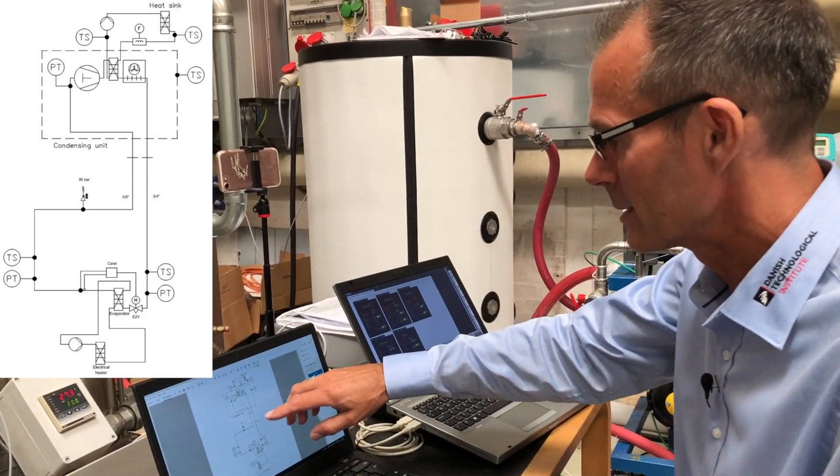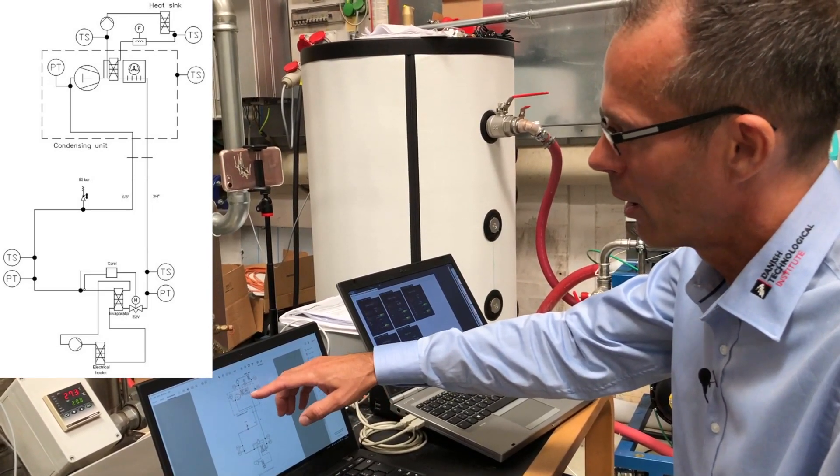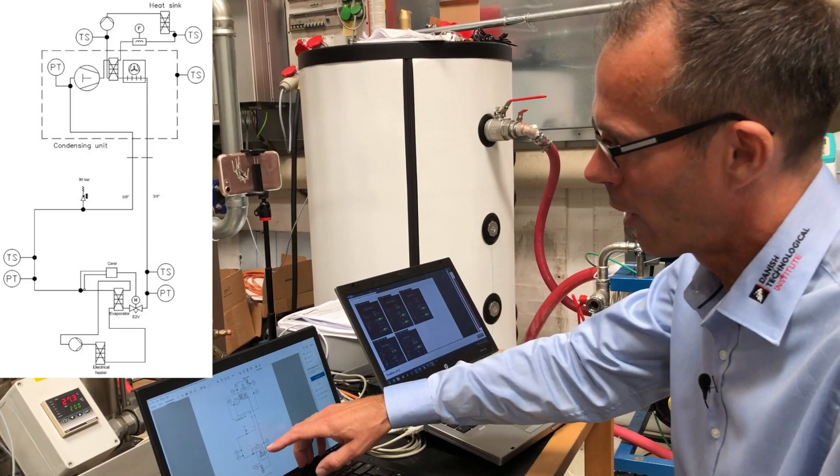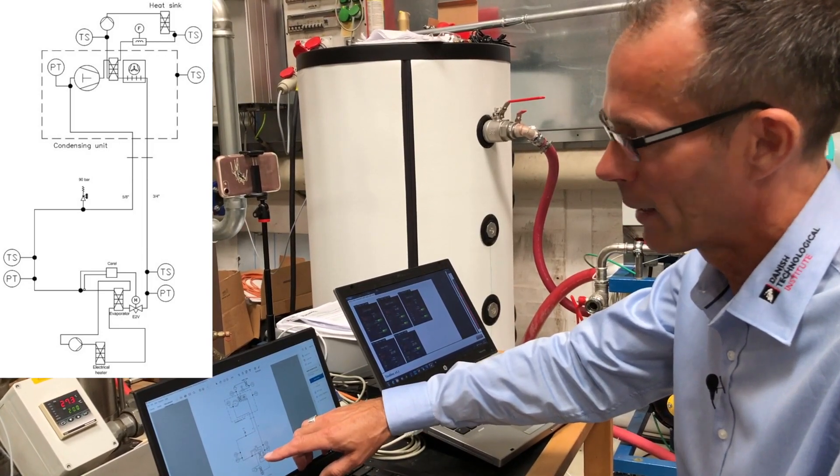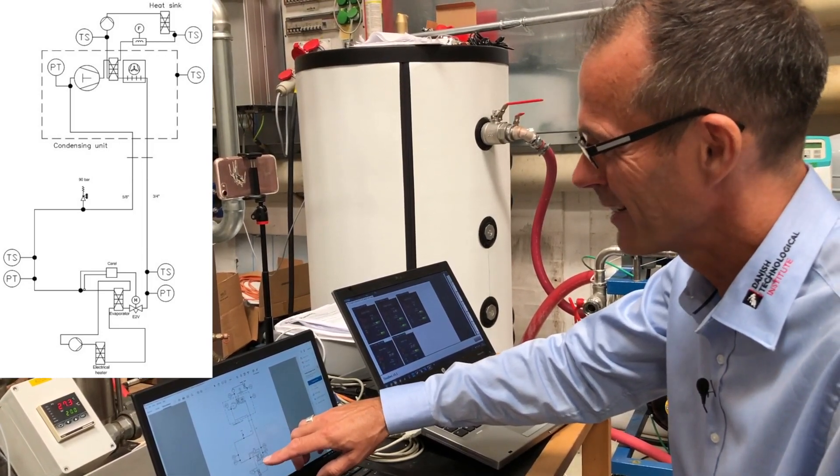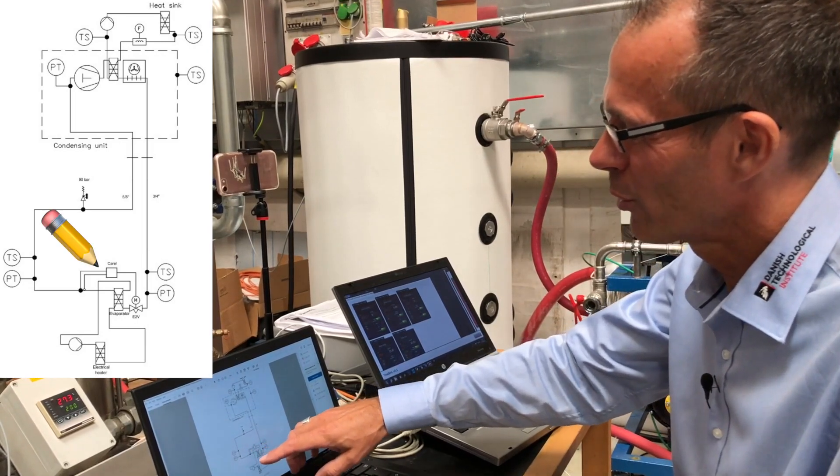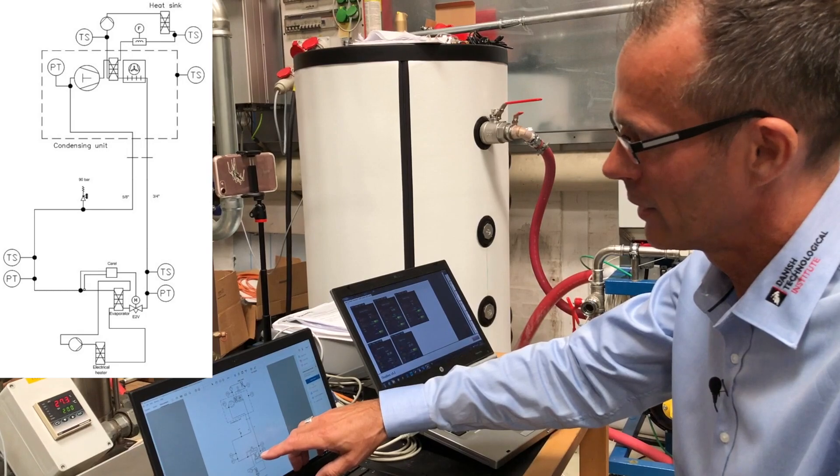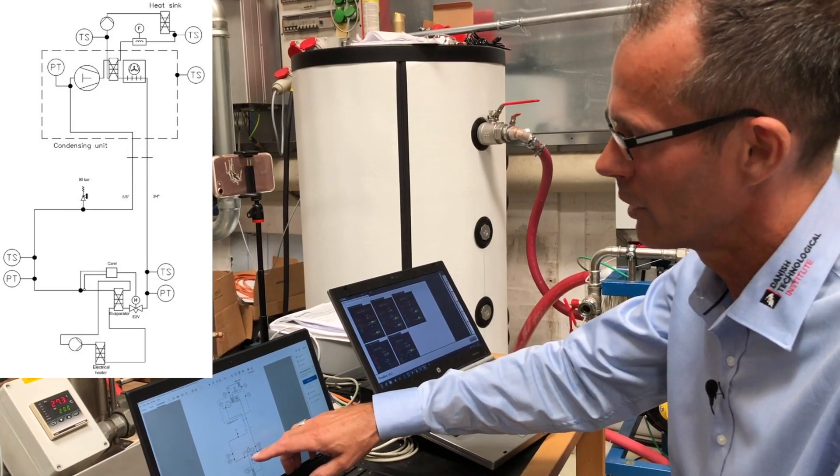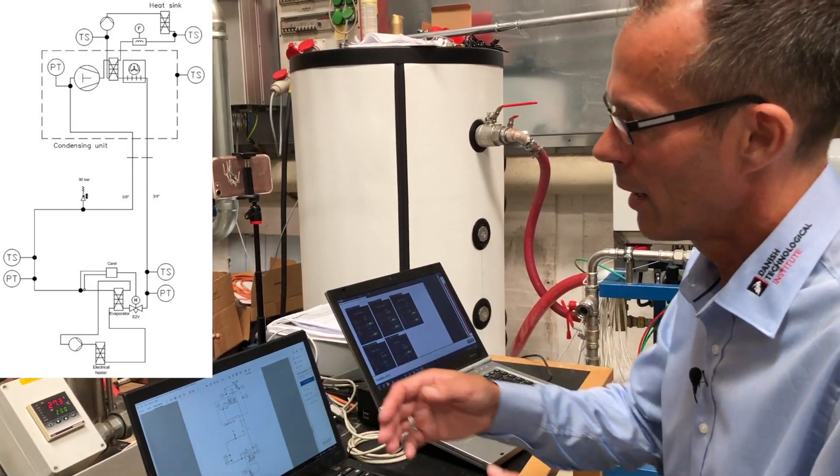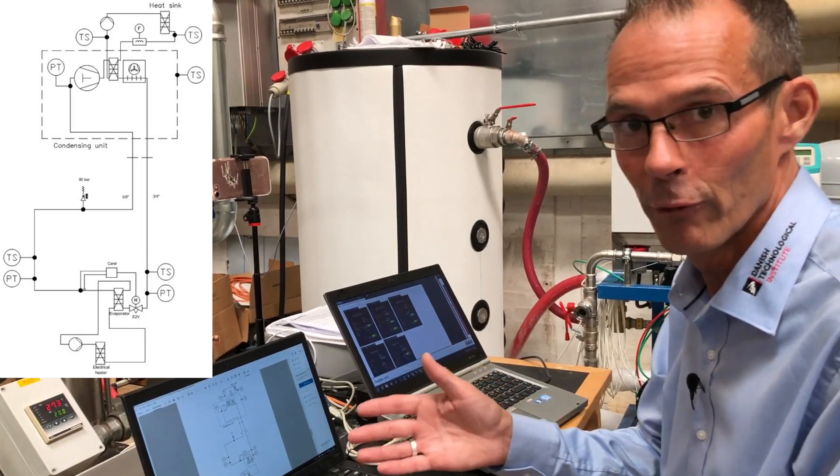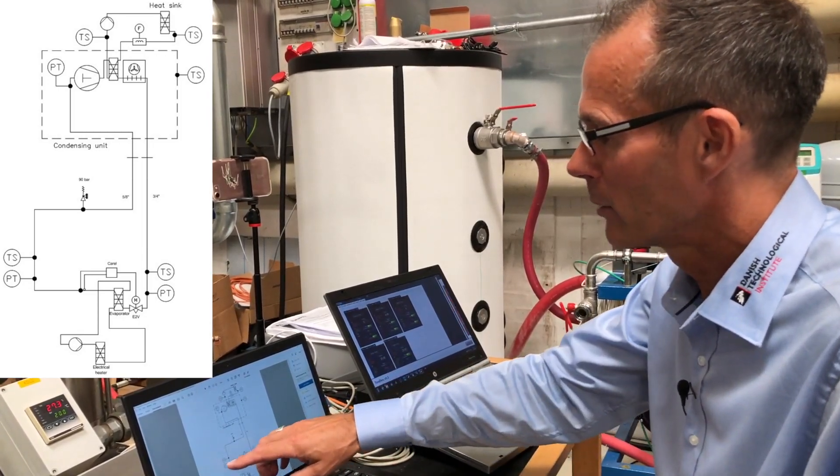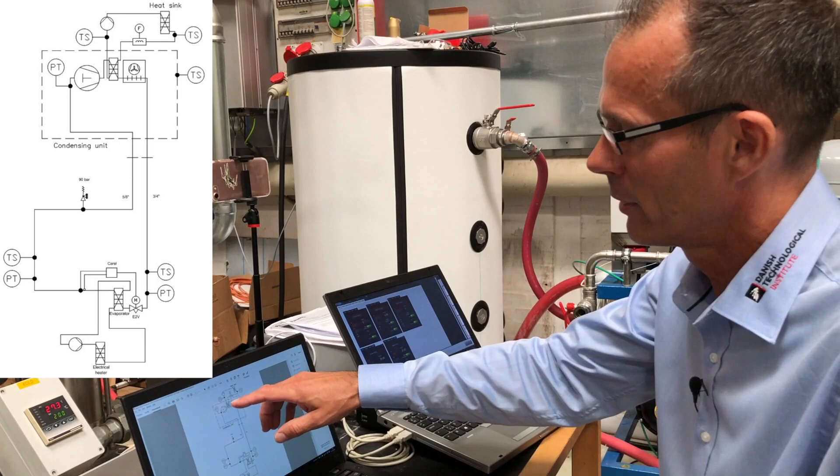The setup is that we are producing liquid for our evaporator controlled by expansion device, superheat controlled. The superheat controller is adjusting the injected liquid to the evaporator and is evaporating to a superheat of 10 degrees and the gas is returned back to the condensing unit.